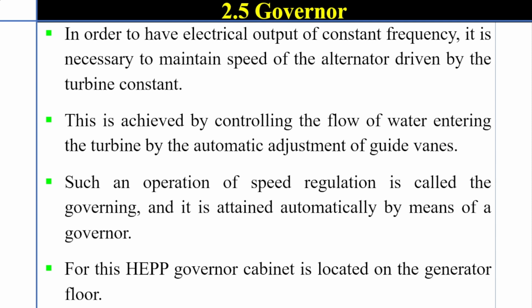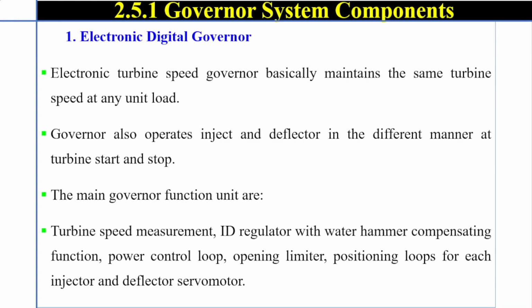Governor. In order to have electrical output of constant frequency, it is necessary to maintain the speed of the alternator driven by the turbine constant. This is achieved by controlling the flow of water entering the turbine by the automatic adjustment of guide vanes. Such an operation of speed regulation is called governing, and it is attained automatically by means of the governor. For this electric power plant, the governor cabinet is located on the generator floor.